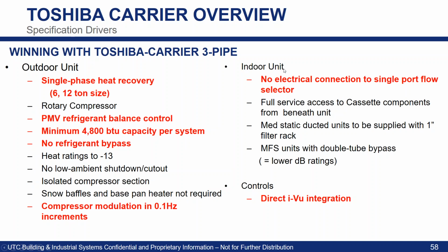Onto the indoor units. This is particular to the single port flow selector, in that you don't need to necessarily run a dedicated electrical feed to that single port flow selector. So if you think about it, you can piggyback the power that flow selector is going to need off of its respective fan coil.